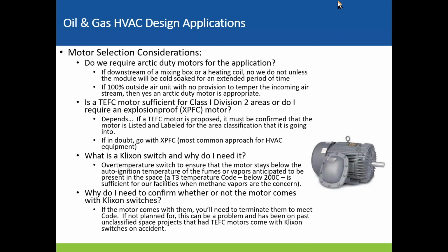Motor selection considerations. One thing that we hear a lot is Arctic duty motors, and when is it right for those? The way I typically approach it is, if it's downstream of a mixing box or a heating coil, I wouldn't use an Arctic duty motor. When you run into trouble is going to be the start-stop of your motor. It will fail if it doesn't have the appropriate pedigree. But if it's 100% outside air unit, it's definitely going to see that minus 50°F or minus 60°F outdoor air temperature.